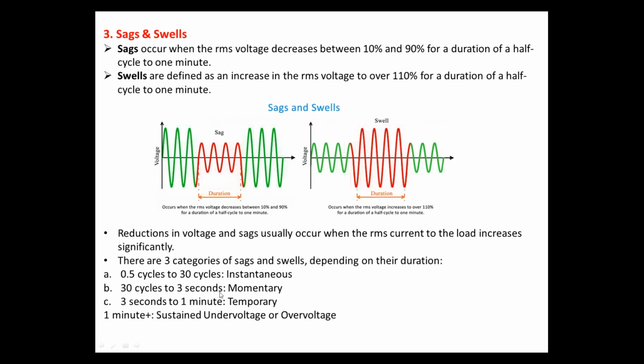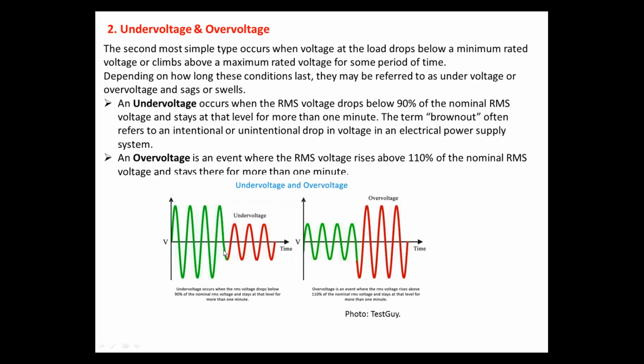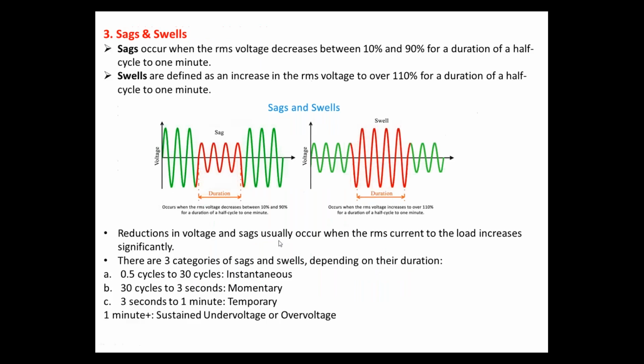0.5 cycle to 30 cycles, it is instantaneous. 30 cycles to 3 seconds, it is momentary. 3 seconds to 1 minute, it is temporary. So such sagging and swelling can occur, and if it lasts more than 1 minute, it comes under sustained under voltage and over voltage. Remember, in case of under voltage and over voltage, more than 1 minute is important, while sagging and swelling is up to 1 minute.